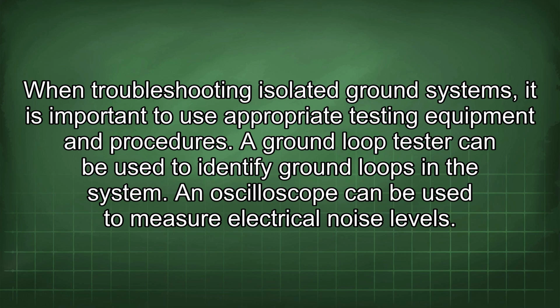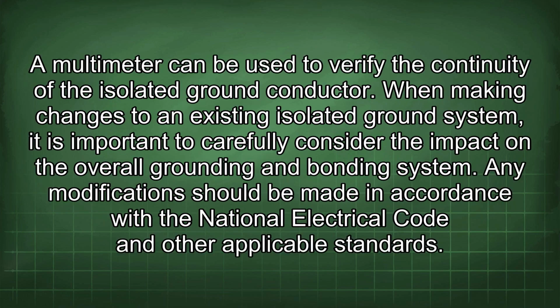A ground loop tester can be used to identify ground loops in the system. An oscilloscope can be used to measure electrical noise levels. A multimeter can be used to verify the continuity of the isolated ground conductor.